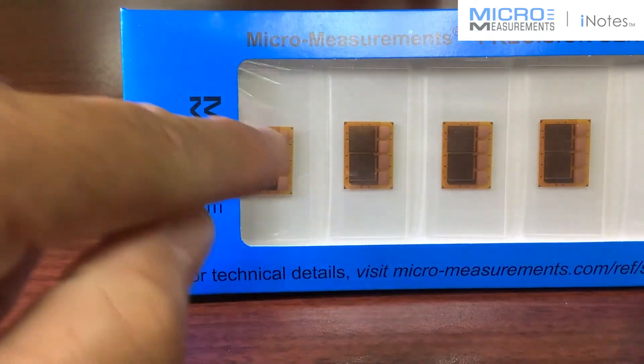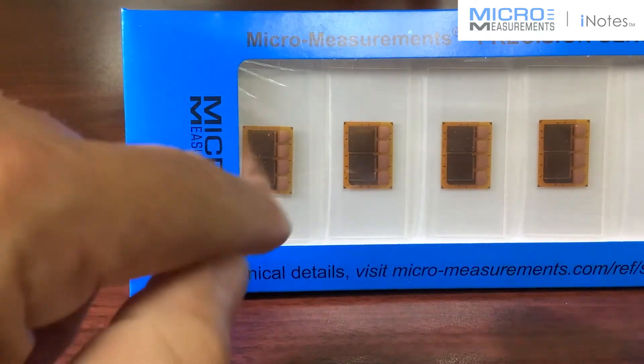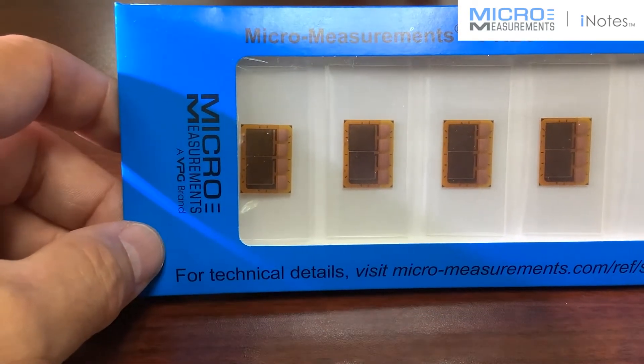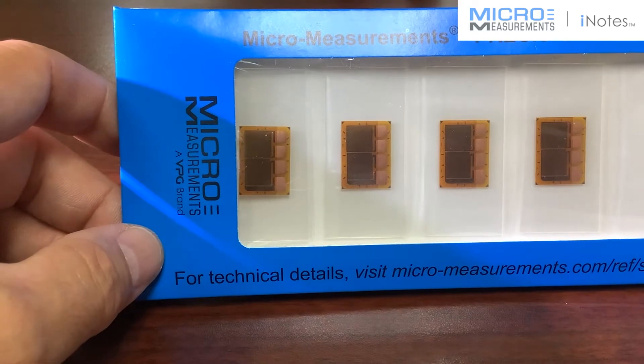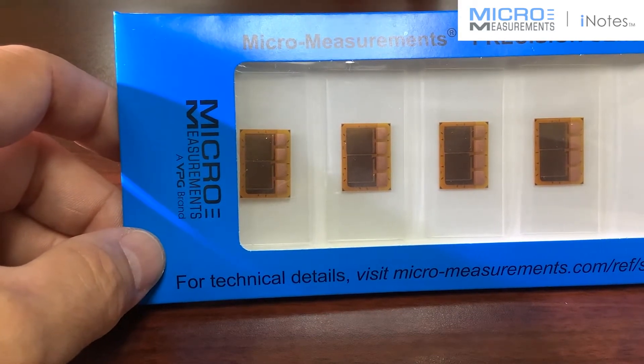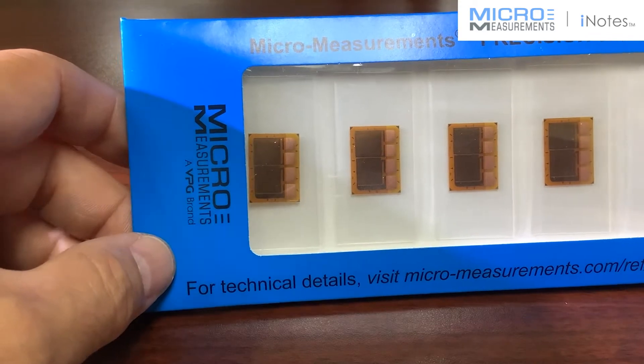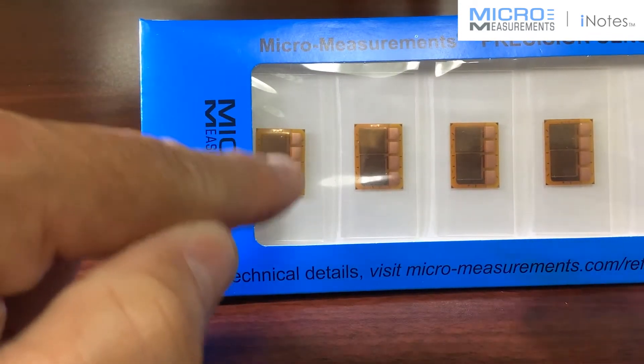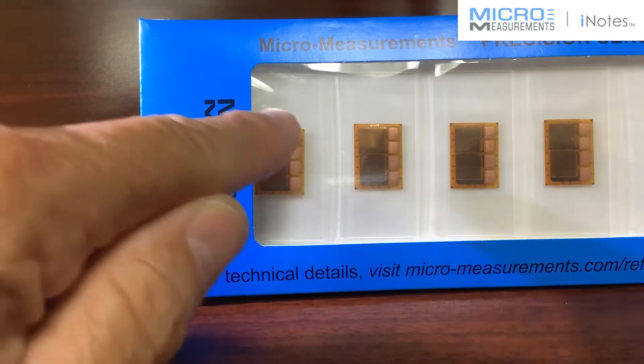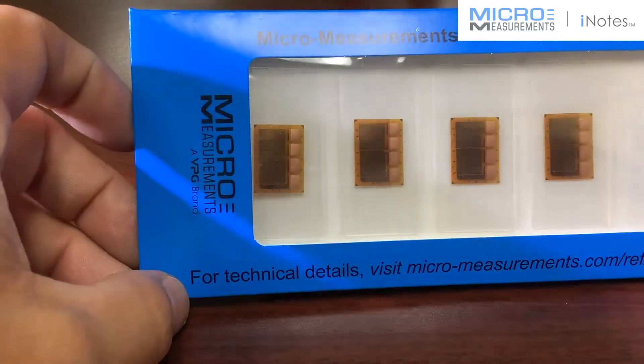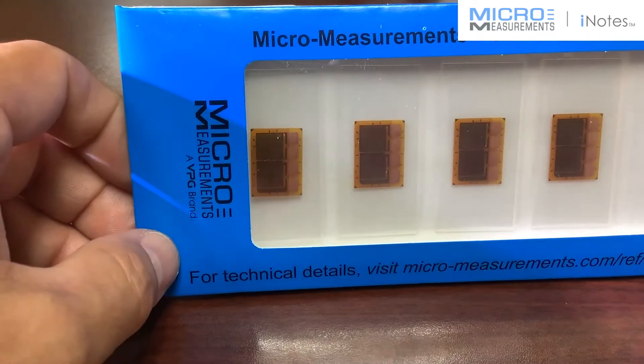This one happens to have the CEA construction that we've offered since the early 1980s, and CEA series gauges have been some of our most popular types of strain gauges for general purpose testing. CEA series simply means that it's got these larger copper-coated tabs that you can see, and there's also a film overlay over top of the grids of the gauge to help protect them while you and I are trying to get them installed.